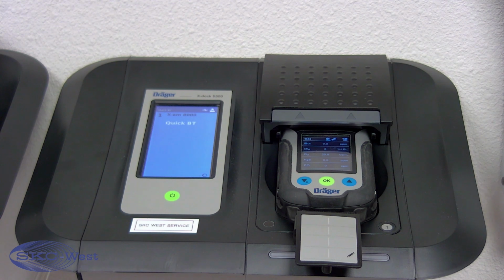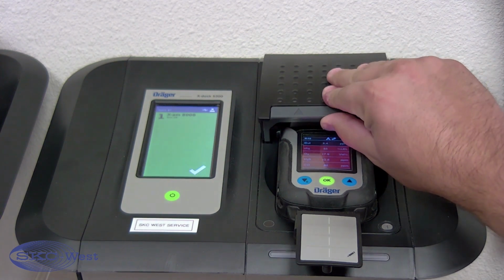Our unit is set up to do a quick bump test, and once it is complete, you will get green check marks on the screen and a green light below the bay. You now know you are ready to use your instrument. If you get a yellow or red mark, do not use that instrument as something went wrong. Once you get the green check mark, you're able to lift the lid and take your instrument out and begin your work.